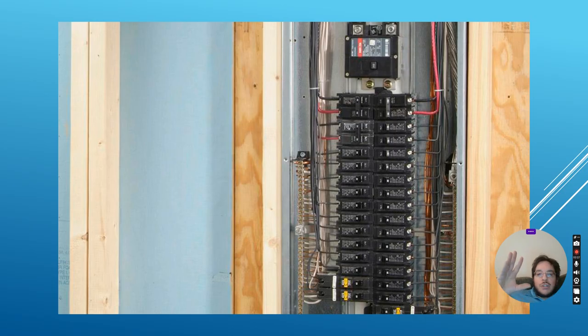It's way cheaper to just put in a 200 amp panel now than having to change the feeders, or the main breaker as required later. So definitely go with a 200 amp panel, and definitely get a big panel so that you've got at least 42 spaces for breakers, so you can add more circuits later. It's always easier to add more circuits to a panel than to say, oh, I'm at capacity and I need to change this thing out.